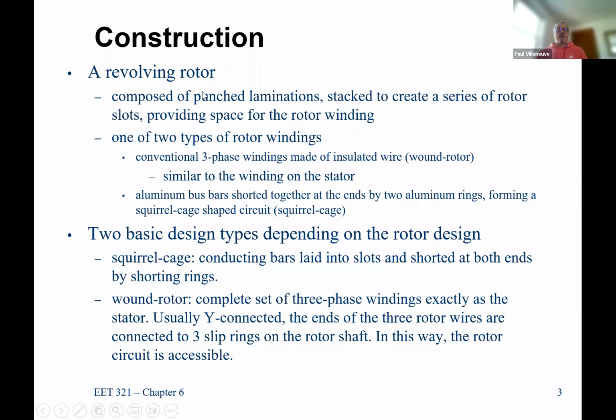So we have our rotating circuit, and we have 2 basic designs. We have a rotor winding that has actual 3-phase windings. Remember how we talked about having an AC field on there. We have to have our AC capability, which means that if we have a 3-phase machine, we need a set of 3-phase windings on our rotor circuit. That's called a wound rotor machine. And you'll see those are used in wind turbines. So, anybody familiar with the type of wind turbine that's been more commonly used in North America and perhaps even in Europe? I believe it's the most common type that they use.